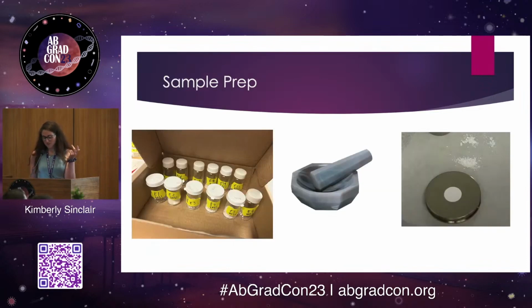Just a quick note about sample preparation. We tried to isolate the mineral phases visually as much as we could from our samples in order to simplify the pattern matching. Grind it up really fine. You want to have good particle statistics for X-ray diffraction, and then dropping it onto a silicon zero background sample holder to try and get that flat homogeneous surface that's so important.